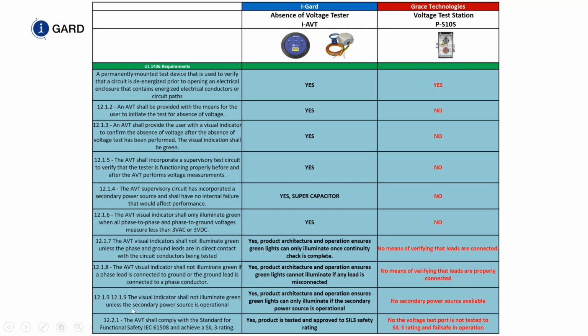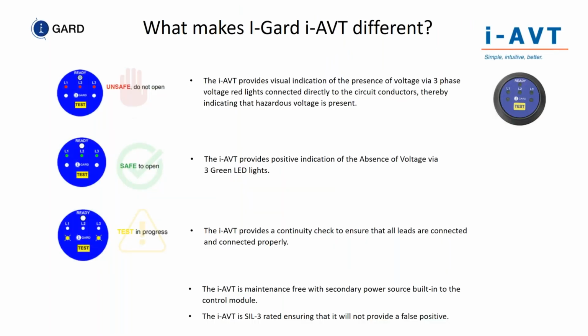The visual indicator shall not illuminate green unless the secondary power source is operational. Yes, if the supercapacitor does not function, you will not get green LEDs. There is no secondary power source on the test station. The absence of voltage shall comply with the standard for functional safety and achieve a SIL rating of 3. Yes, this is a very, very stringent test. There's only a couple of relays or devices that actually meet this standard, and the IAVT is one of them. The voltage test station does not meet that standard. It does not have SIL3 rating.